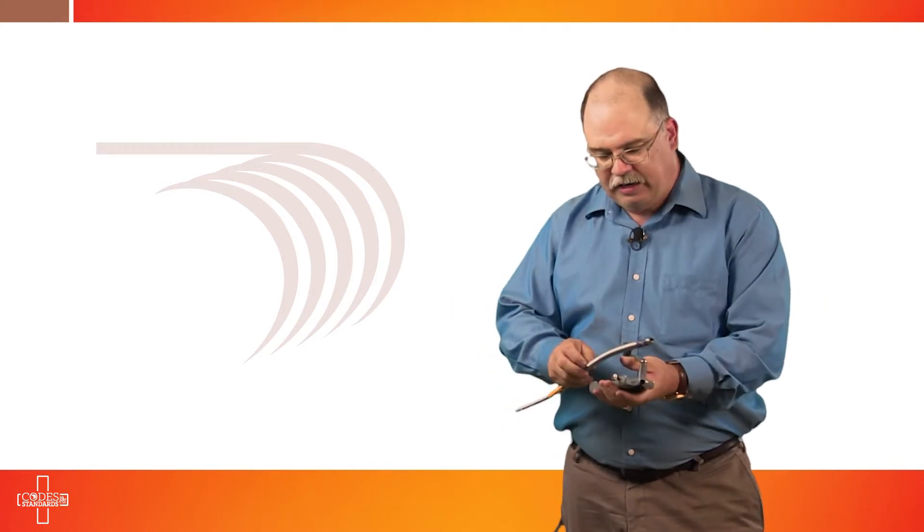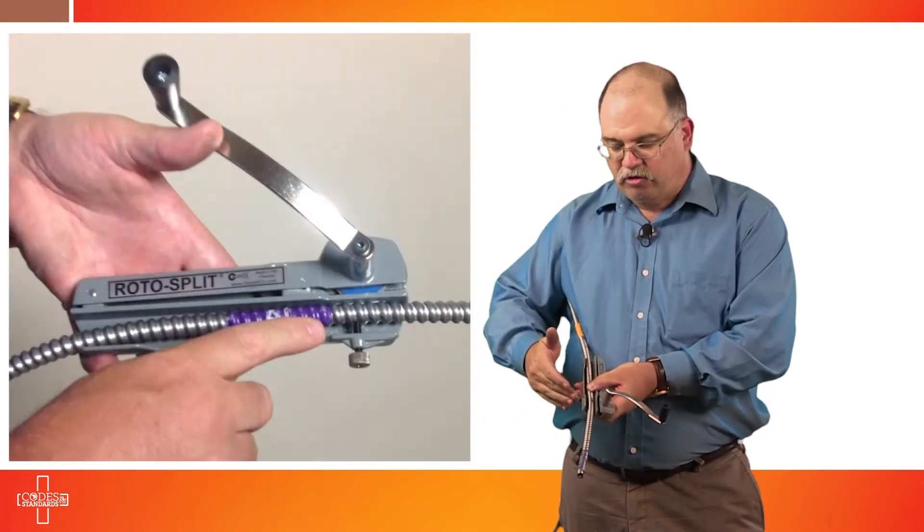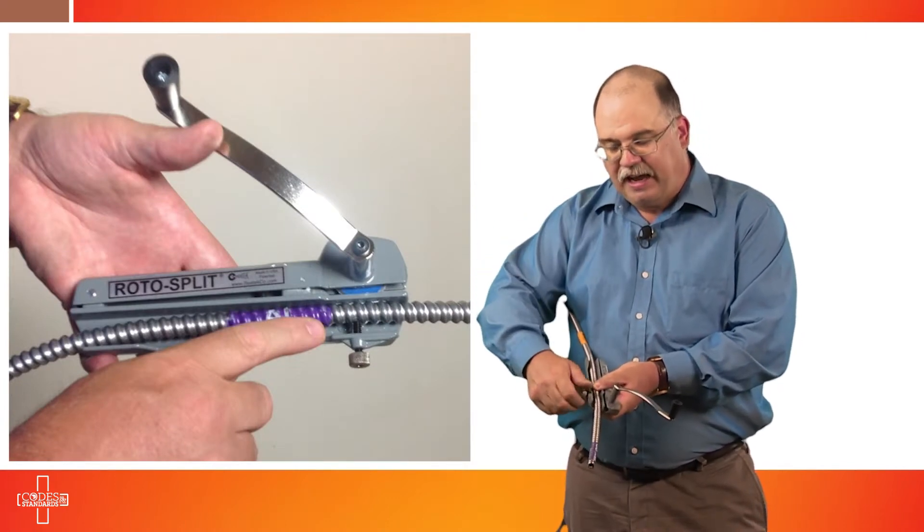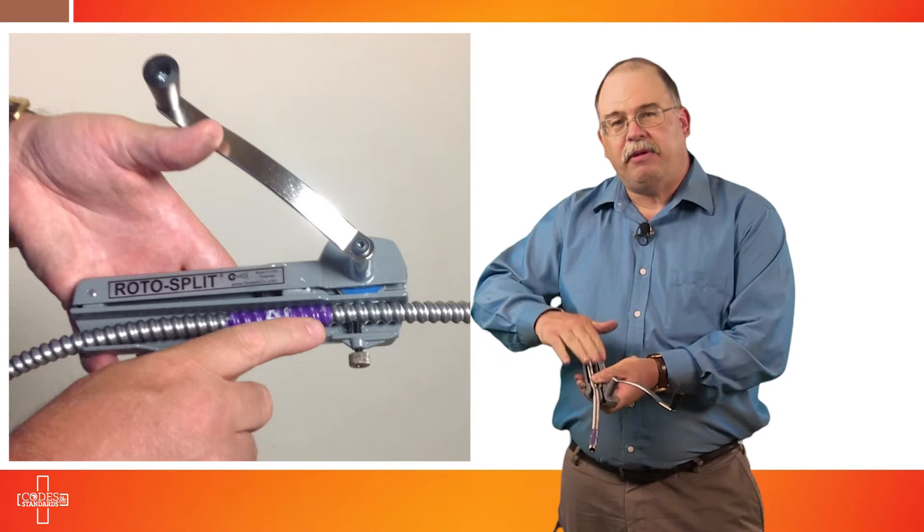We've determined that we need about 8 inches of open conductor. In other words, we need to remove the metallic sheathing to expose 8 inches. So what you do is select where you're going to start your cut in order to expose those conductors. We place it into the tool. Now this tool has a set screw that you would loosen, place the cable in, and then tighten down. And that holds the cable in place in order for you to be able to cut it.